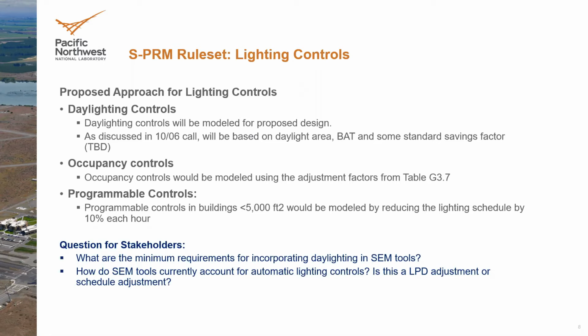No - I guess what Energy Plus is doing internally is probably an LPD adjustment happening at a scheduled time based on what the daylight is to the space. So it's probably doing both: depending on the incident daylight on the space and its calculated reduction in foot candles needed, it reduces the LPD for that hour or time step by a certain percentage. That's actually doing daylighting right, baked into the model since it's available in Energy Plus.